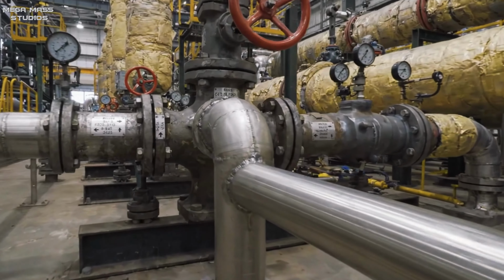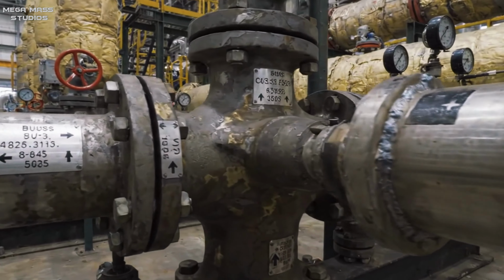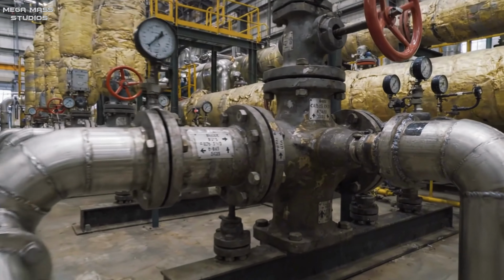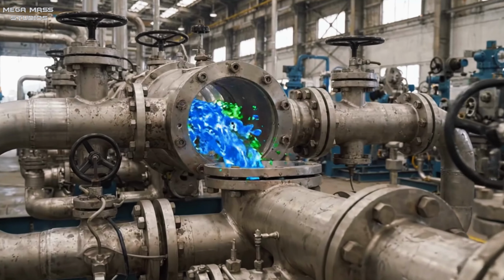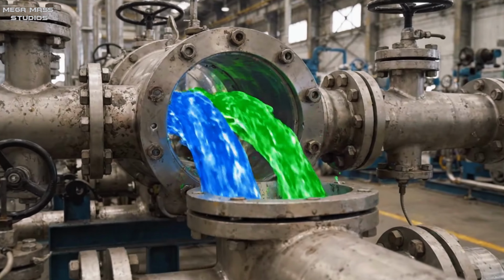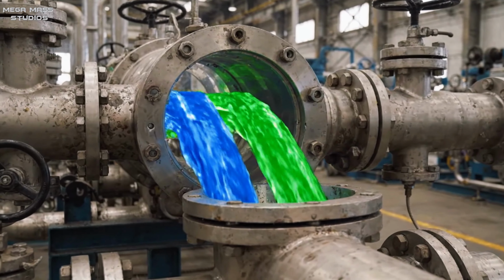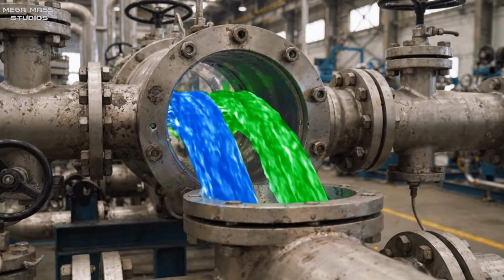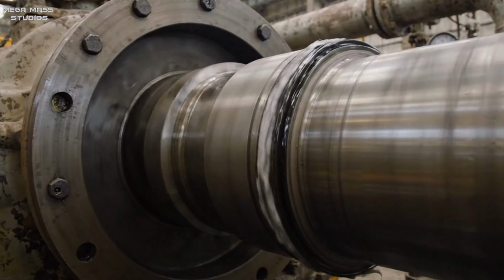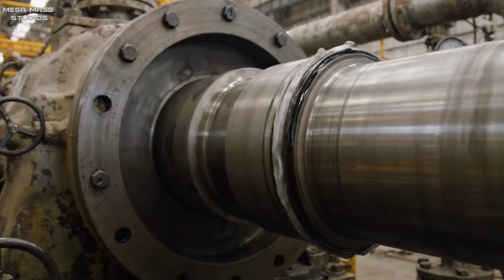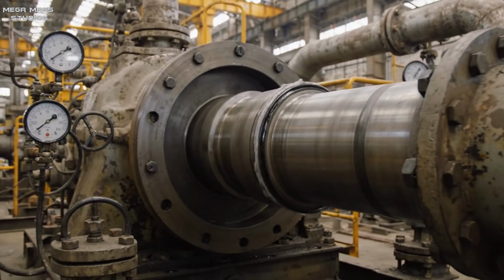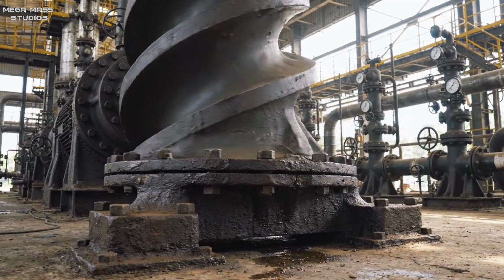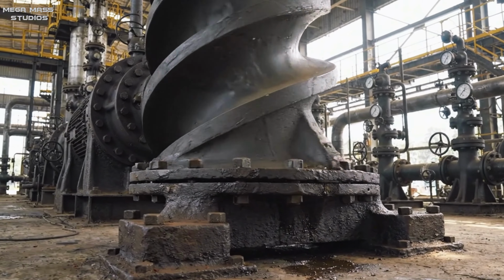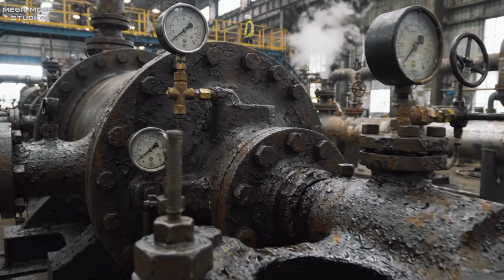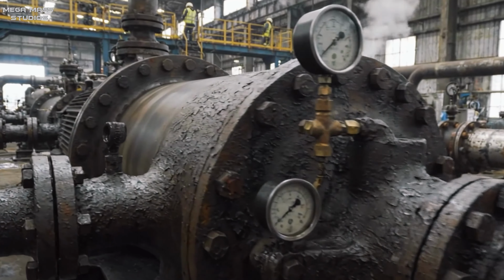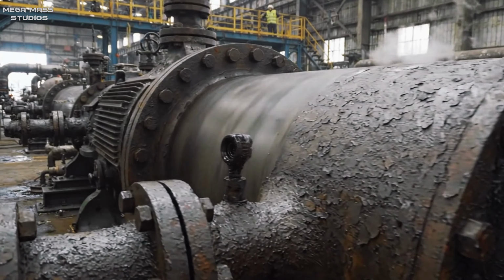To counteract this, specialized hydraulic bypass loops inject high-pressure water directly back into the suction throat. This re-injection process stabilizes the local velocity vectors, restoring a smooth laminar fluid intake profile. The water now enters the main impeller eye, where kinetic rotation translates directly into static pressure. The centrifugal force flings the water outward through the spiral volute casing at incredible speeds. This spiral casing is engineered with expanding dimensions to slow the water down and maximize pressure conversion.